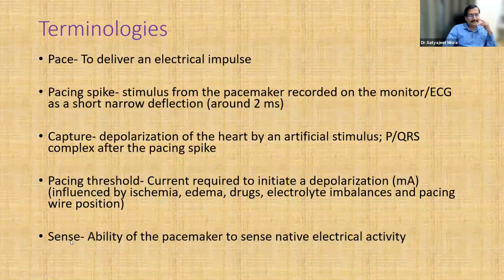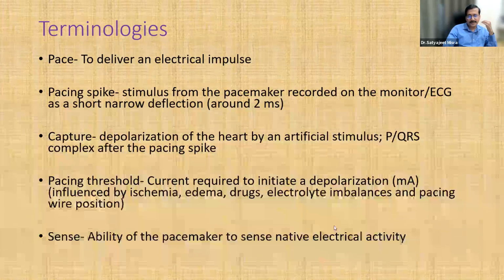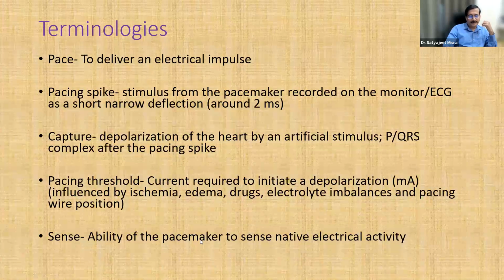What's sense is whether the pacemaker is able to sense the native electrical activity. So how sensitive is the pacemaker to detect the native electrical activity? And this is important because if there is native electrical activity, then that should be allowed rather than the pacing activity by the pacemaker. So these are the common terminologies that you will always come across when you're dealing with pacemakers. So it's important to understand this terminology.